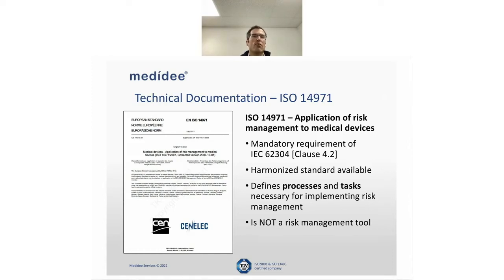So if you're starting your project with regard to medical devices, I would clearly invite you to go and look at this standard, because risk management is really the way you justify all decisions you will make with your device. You cannot really expect, until you reach the end of your design phase, to say, okay, now I start to look at the risk associated with my device, because it's very likely that risk will be addressed through the risk management process, through the design. So you will actually have to take the risk measures or the risk controls along with the design of your process. So it's really important that you look early at these standards.